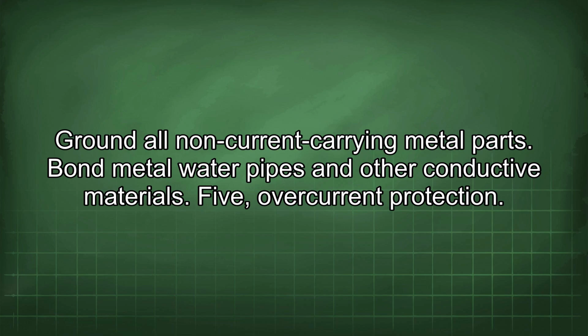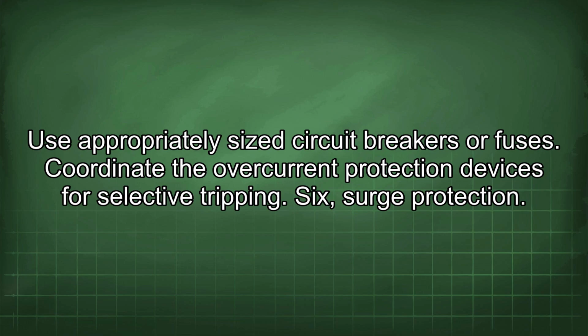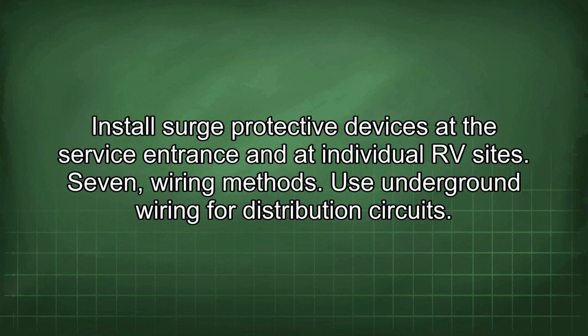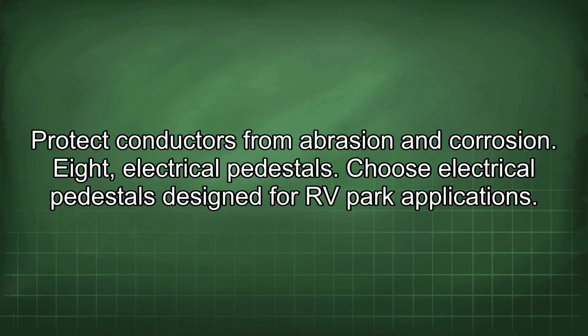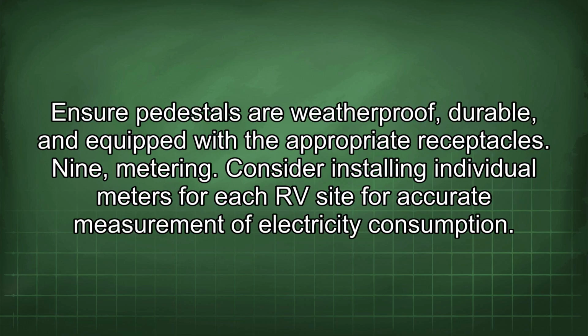5. Overcurrent protection. Use appropriately sized circuit breakers or fuses. Coordinate the overcurrent protection devices for selective tripping. 6. Surge protection. Install surge protective devices at the service entrance and at individual RV sites. 7. Wiring methods. Use underground wiring for distribution circuits. Protect conductors from abrasion and corrosion. 8. Electrical pedestals. Choose electrical pedestals designed for RV park applications. Ensure pedestals are weatherproof, durable, and equipped with the appropriate receptacles.